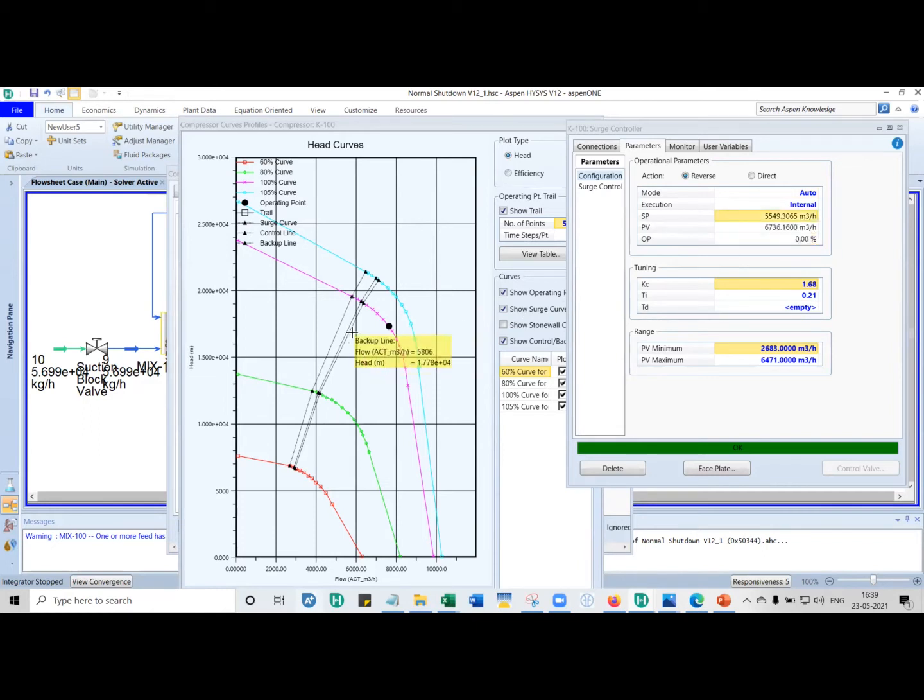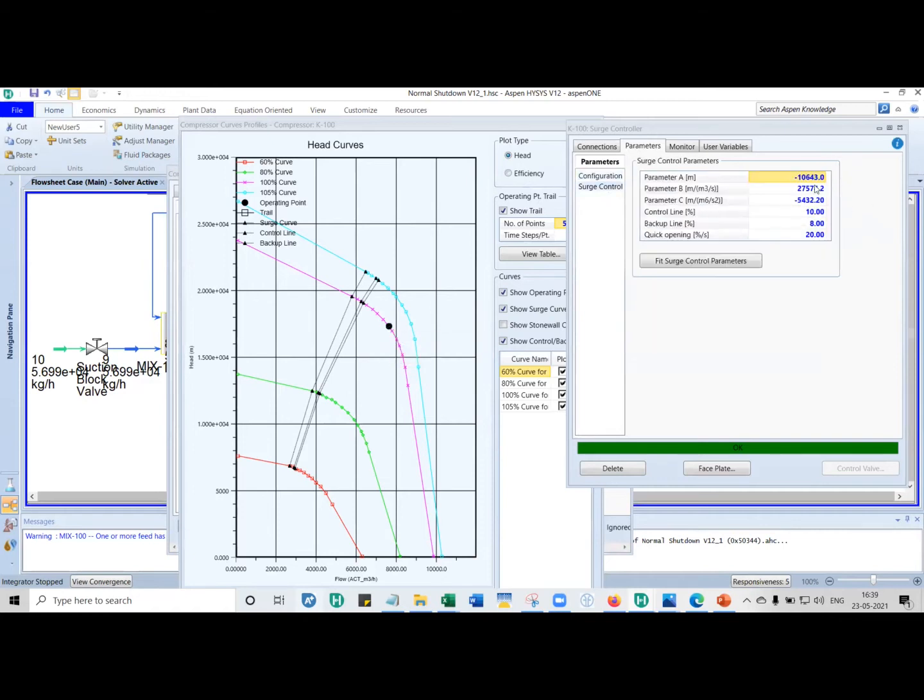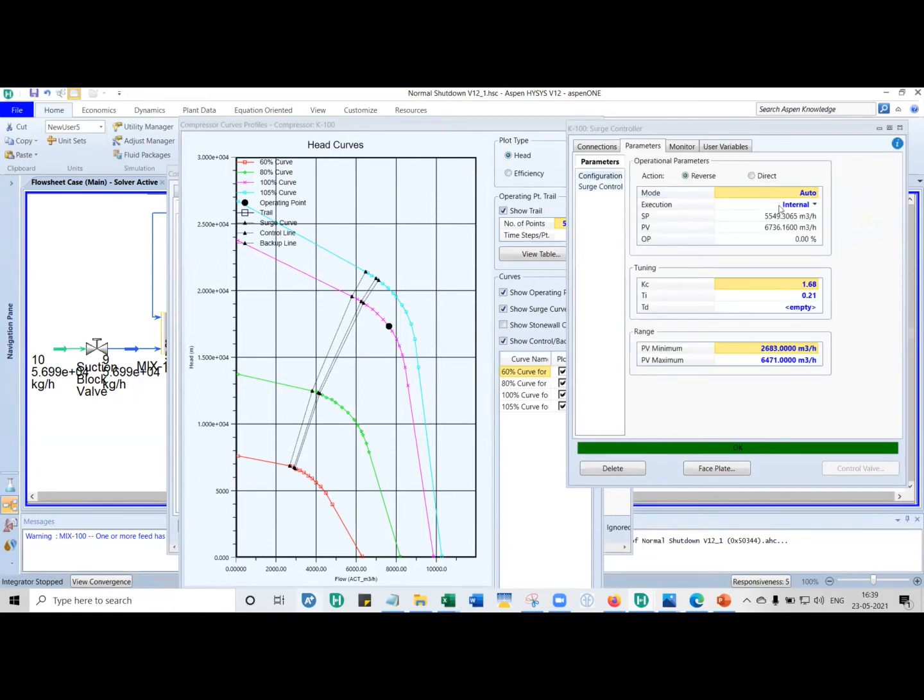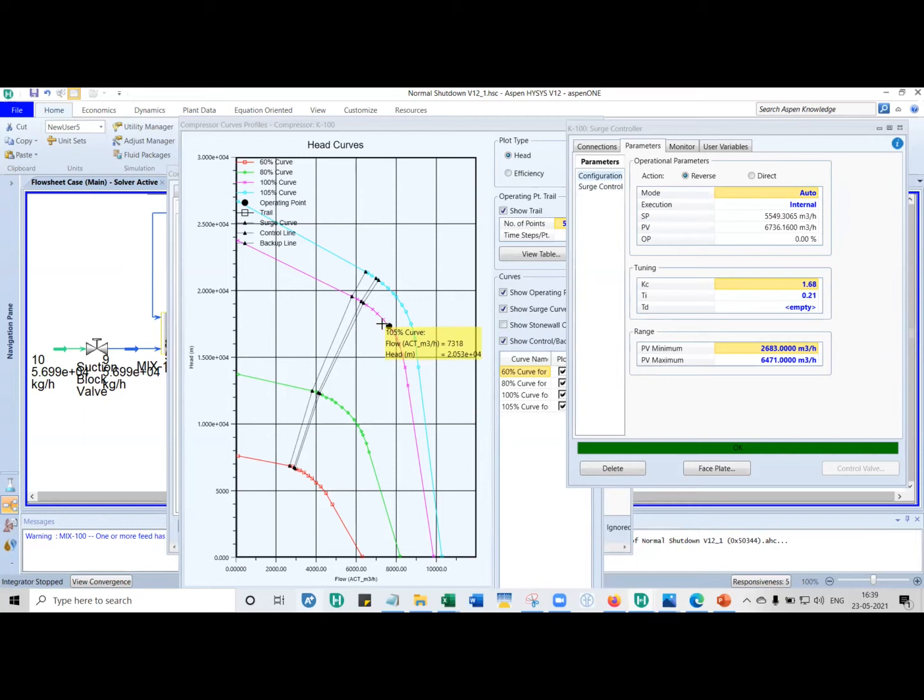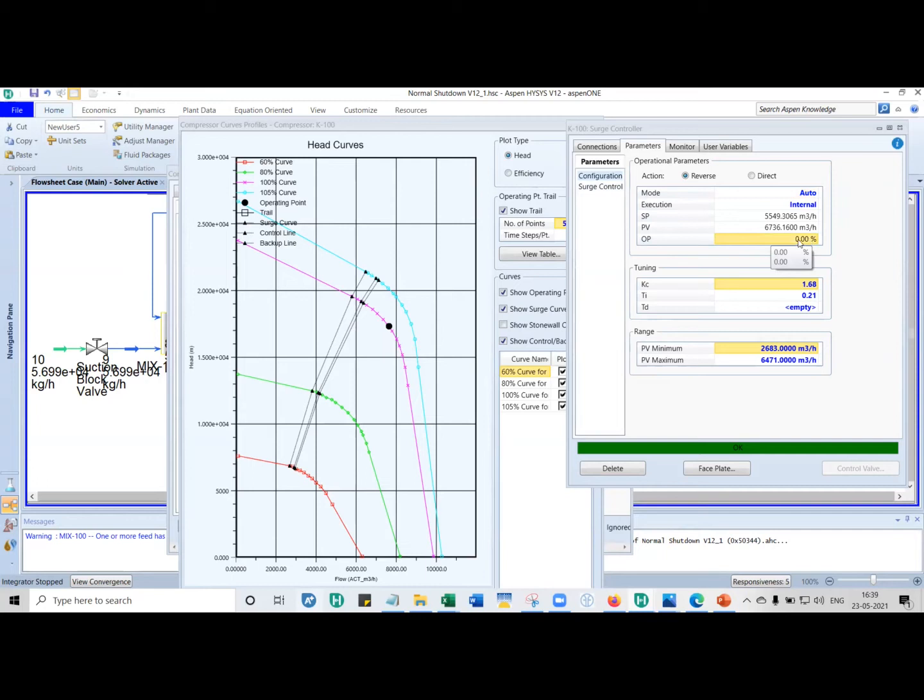Set point is how far is it away from the control line. Process variable is where is it currently. With the coefficients, you're estimating how much should be the head. And based on the distance, the anti-surge controller decides how much recycle flow do I need to recycle. Here in this case, OP is the valve opening. This percentage is actually the ASV opening.